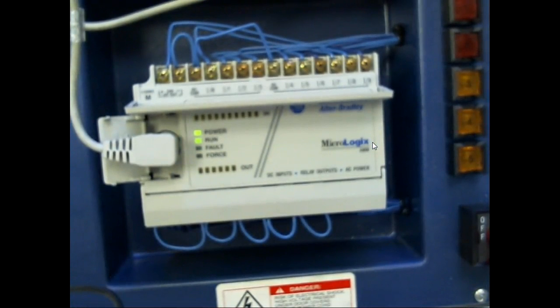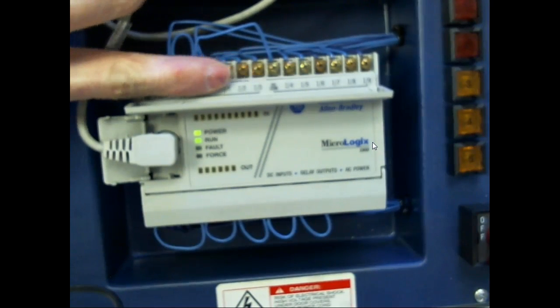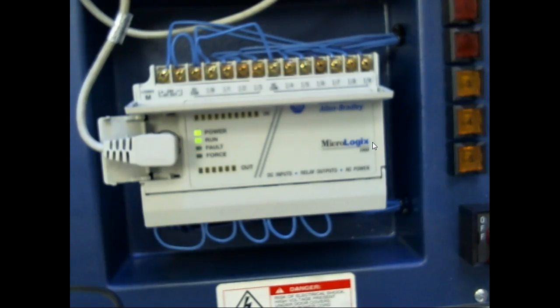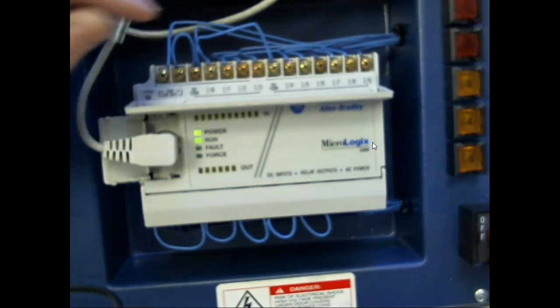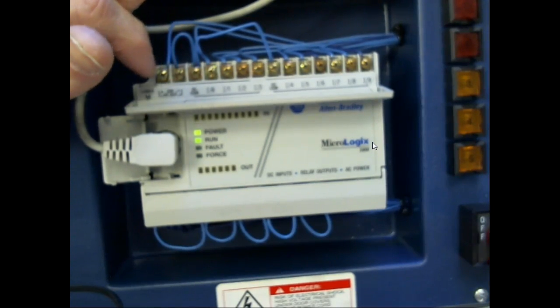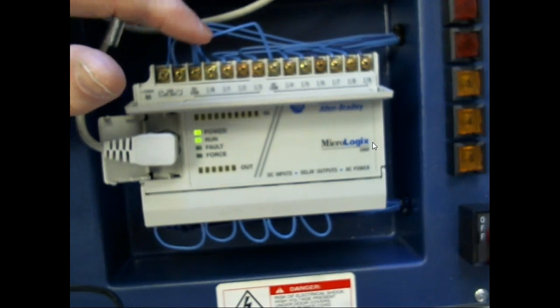What's neat about Allen-Bradley, well, I wish this thing would focus. Good gracious. Come on, focus. What this does is these are configurable inputs. So you can't see it, but that's DC common, that's DC common. So what you do is you can set these up as either sinking or sourcing inputs, whatever you use as a common, but it's DC. What they're doing is they're taking the minus, so this is minus DC right here. I'm pointing to it on my computer. So this is plus DC, this is minus DC, and they've got this jumped to the common on this one, and then they've got it jumped to the common on that one. So that means that the PLC is set up to sink.